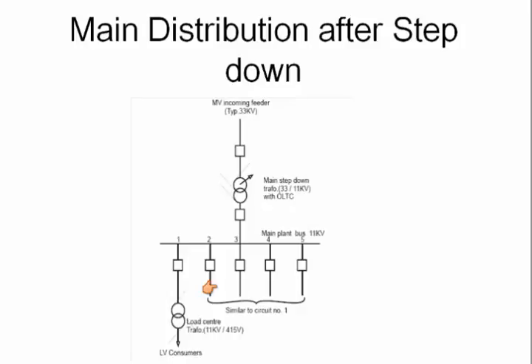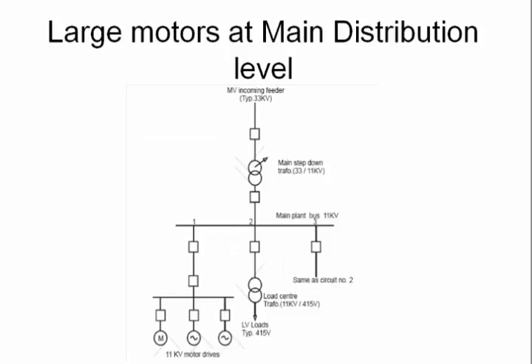Large motors typically might run at medium voltage because higher the voltage, smaller the current. When the current is smaller, what happens to your voltage drop? It reduces. What happens to your losses? It reduces. So the system voltage is not affected much. If you run too many motors at low voltage, the starting current is quite high. That can significantly impact your voltage. And because of the undervoltage, other loads can suffer as well. Some of the motors may fail to start.